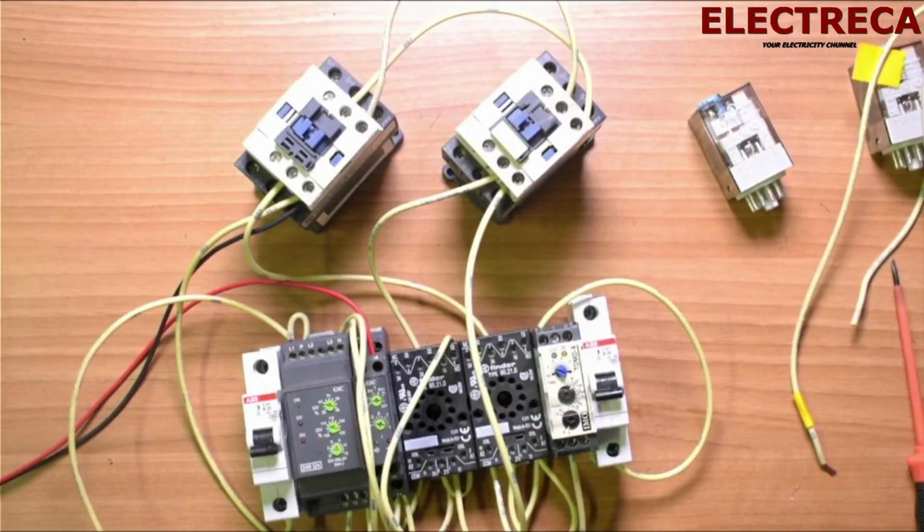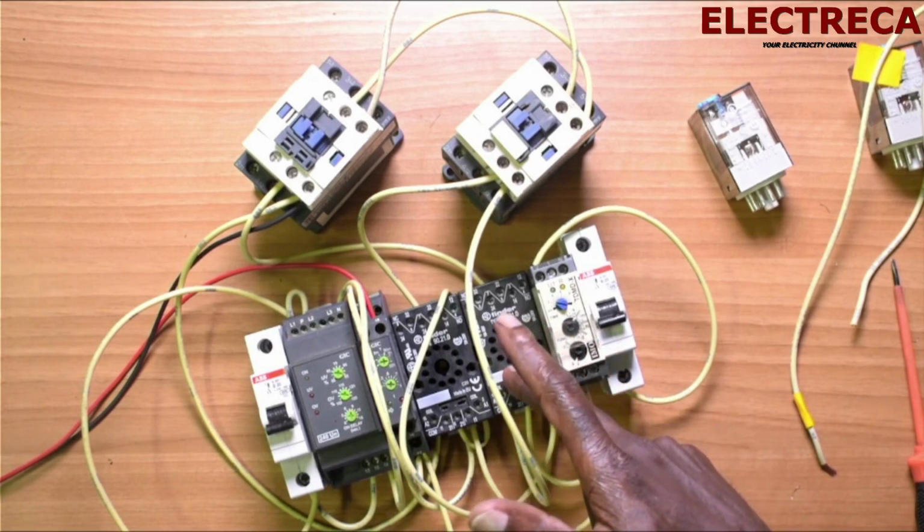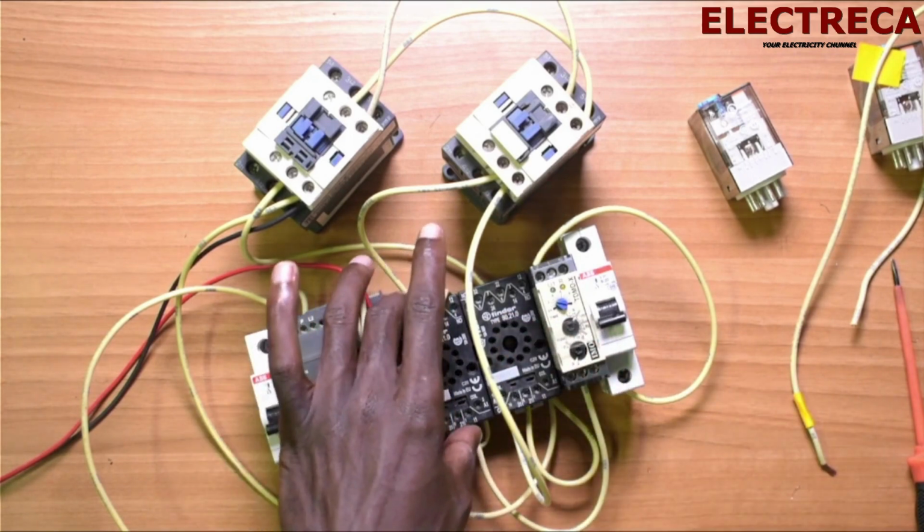Now, I have finished this part for the wiring, so we are just going to the generator lobby, and then we grab a 10 kVA so that we can put our changeover switch at test. Now before we go any further, this is a changeover that is done. So we have a Gen relay and we have a main relay. On this main relay, as I said earlier, that's where our generator signal is going to be, and you will see as we go to the generator. So let's go to the Gen lobby, and then we have all these things connected together. Let's go to the lobby.